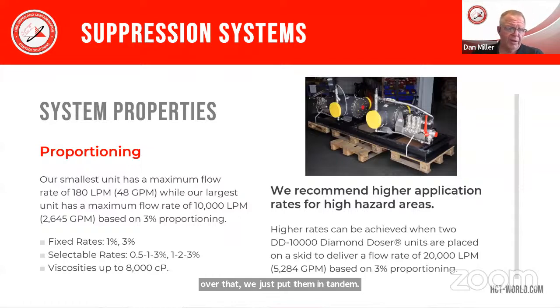So proportioning: the smallest Diamond Doser unit is 48 gallons per minute or 180 liters per minute. And the largest unit is 2,600 gallons per minute or 10,000 liters per minute. And that's with 3% proportioning fixed. You can have fixed rates of 1 or 3%. We do have portable models available with selectable proportioning, and you can use different viscosities. It doesn't have to be F500. You can use Newtonian, non-Newtonian liquids with a viscosity of up to 8,000 centipoise.